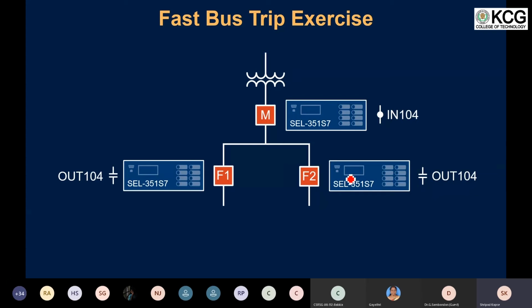And due to some reason, let us assume that the fault occurs on the bus bar. If the fault occurs on the bus bar, then that fault is not seen by the relay protecting the outgoing feeder. It is only seen by the incomer relay. But this incomer relay is time coordinated to operate with a delayed operation time, which means a large fault current, or a large amount of arc flash energy, could be created because of the delayed operating time of the relay.